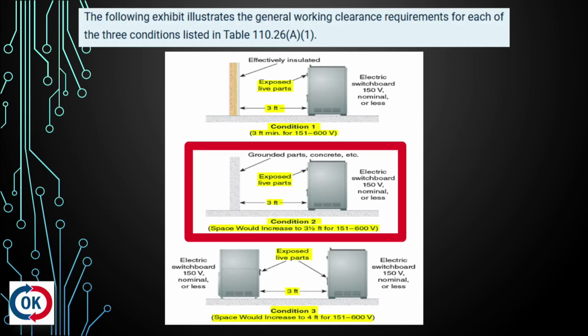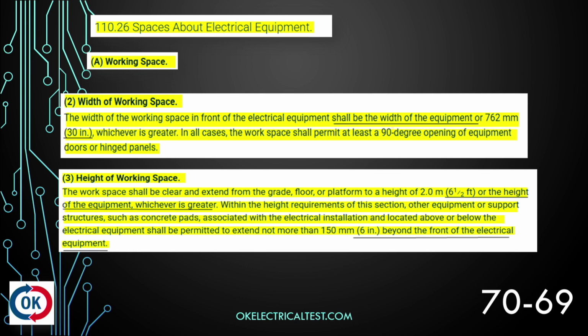Now A2 is dealing with the width of the working space. So how wide does it need to be? It says the width of the working space in front of the electrical equipment shall be the width of the equipment or 30 inches, whichever is greater. It goes on to say that in all cases, the workspace shall permit at least a 90-degree opening of equipment doors and hinged panels. So when we take this measurement, it's based off either the width of the equipment or 30 inches, whichever is greater.